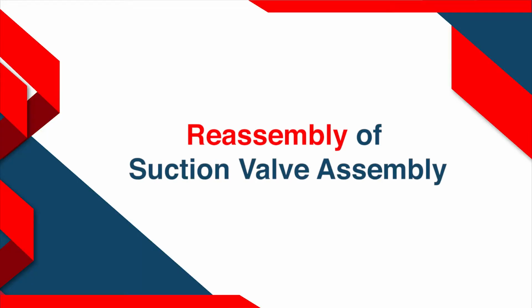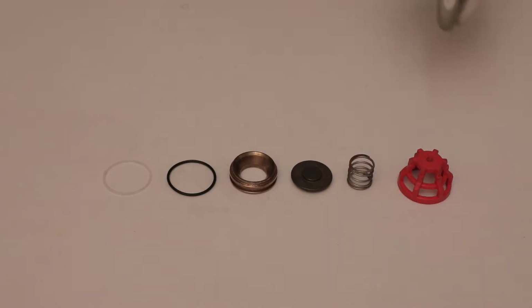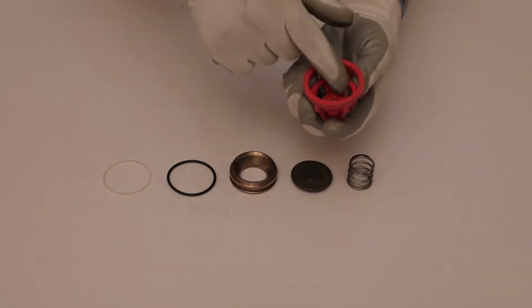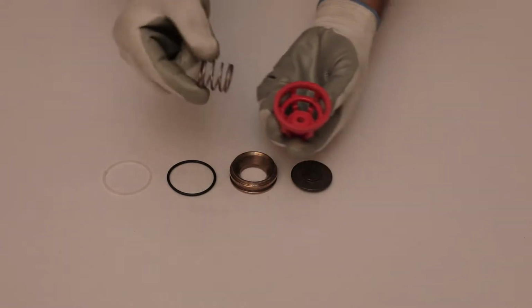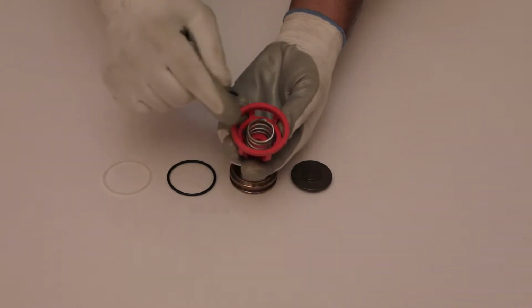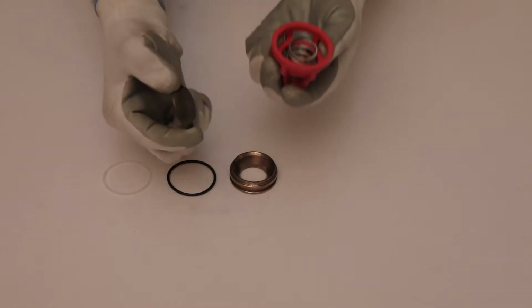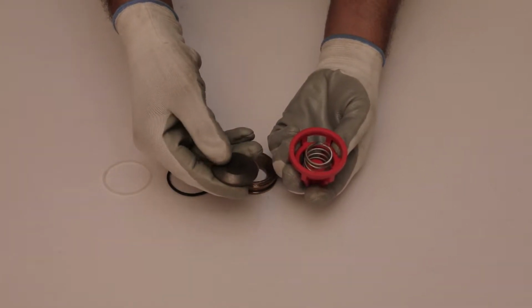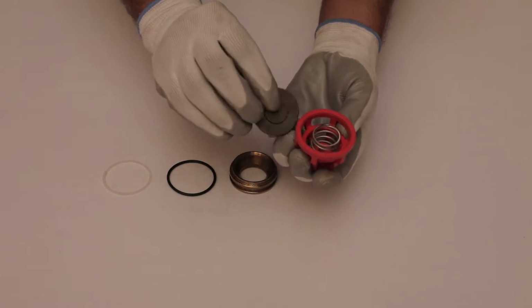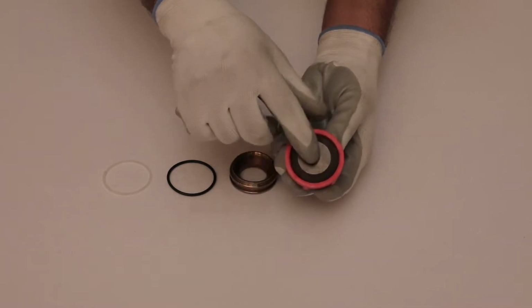Reassembly of suction valve assembly. Take suction and discharge valve guide and put helical spring in its proper position. Place suction and discharge valve plate on spring such that portion having step will be facing to the spring.